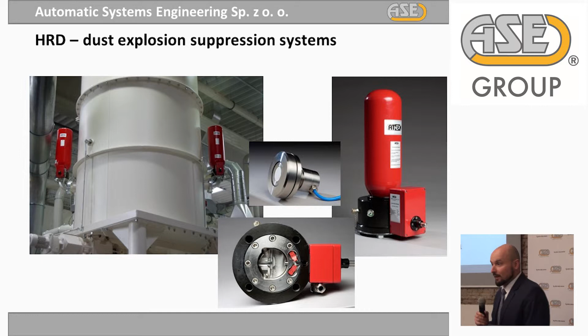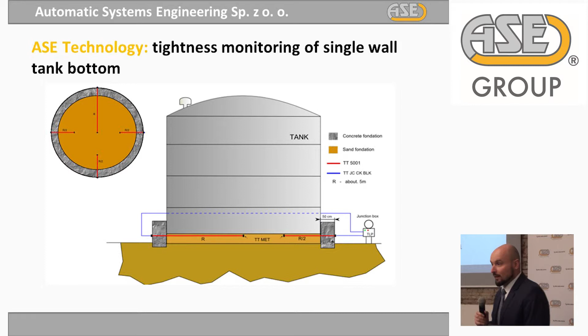Tightness monitoring of single wall tank bottoms is our own technology. We developed it especially for old tanks where there is no other way to make them safer. We install special pipes and cables under the tank bottom to look for leakages.